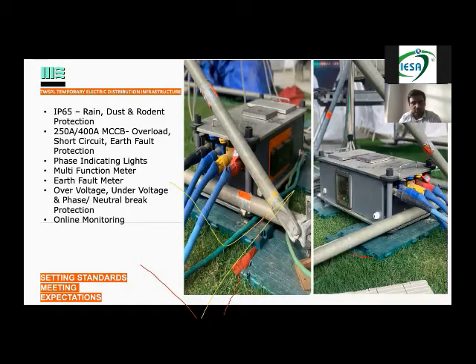0 to 30 mA is acceptable. When I say mA, it is milliamps. Milliamps is acceptable. Anything above 30 mA, the system will trip. Then over voltage and under voltage protections. Again, we've given that if over voltage comes, the MCCB will trip. If there is under voltage, then also the MCCB will trip.